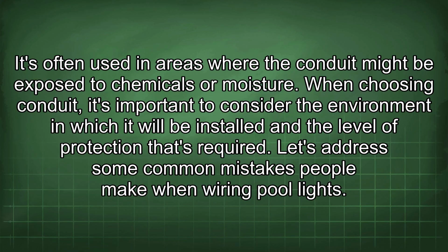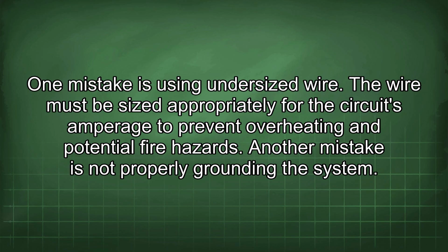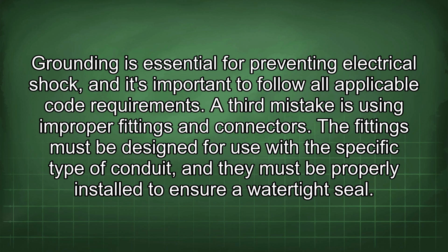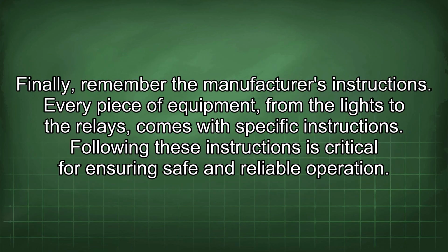Let's address some common mistakes people make when wiring pool lights. One mistake is using undersized wire. The wire must be sized appropriately for the circuit's amperage to prevent overheating and potential fire hazards. Another mistake is not properly grounding the system. Grounding is essential for preventing electrical shock, and it's important to follow all applicable code requirements. A third mistake is using improper fittings and connectors. The fittings must be designed for use with a specific type of conduit, and they must be properly installed to ensure a watertight seal. Finally, remember the manufacturer's instructions. Every piece of equipment, from the lights to the relays, comes with specific instructions. Following these instructions is critical for ensuring safe and reliable operation.